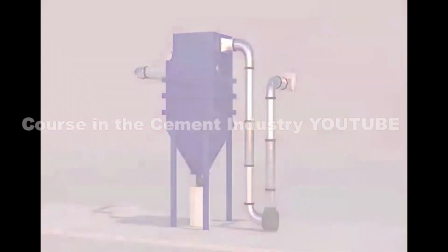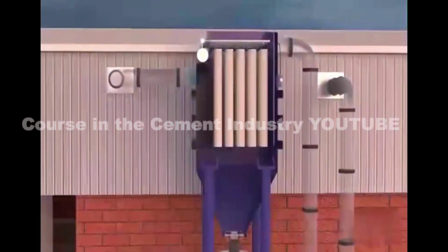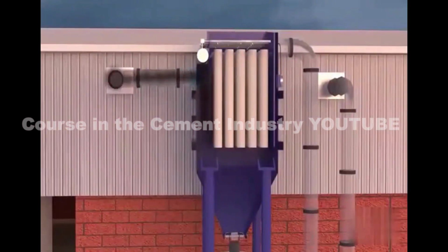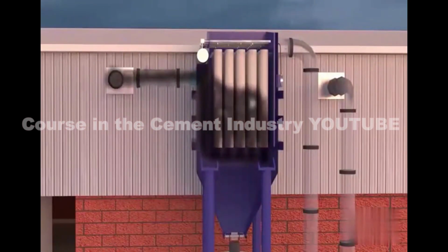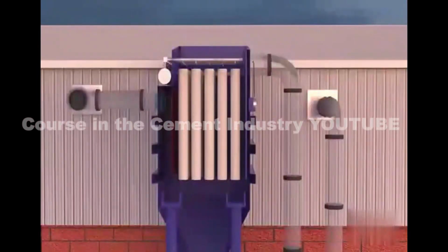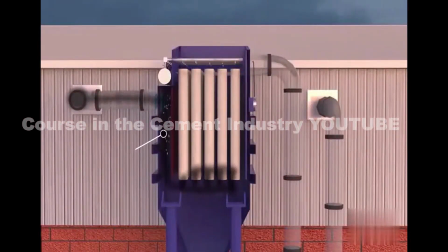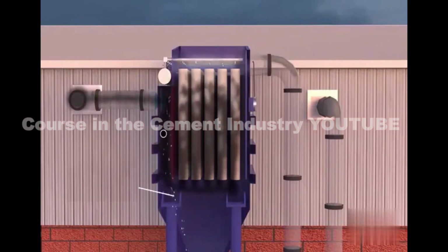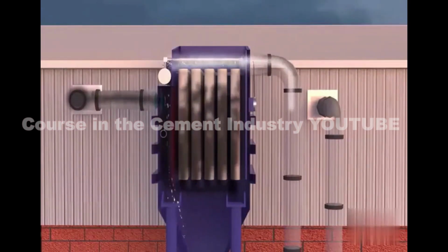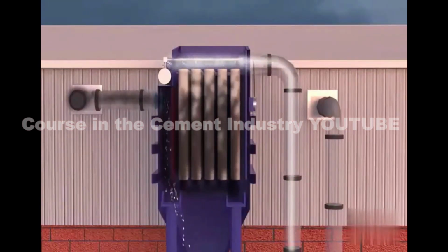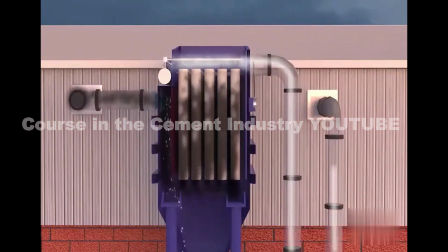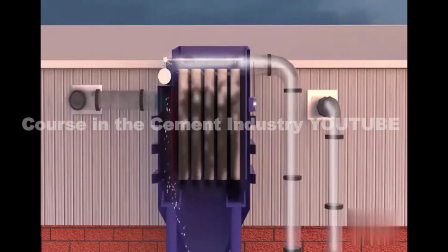Now let's understand how this works. Working. The contaminated air enters the system through the inlet and passes through the filter bags. Due to the use of a baffle plate, the heavy particles fall down into the hopper and the lighter dust particles get deposited on the exterior surface of the bags, allowing only the cleaner dust-free air to pass through the filters and then upward in the clean plenum. The clean air is then discharged outside. This is the general process that takes place in the system.